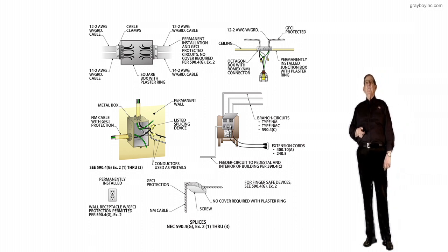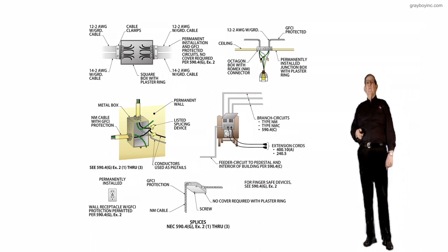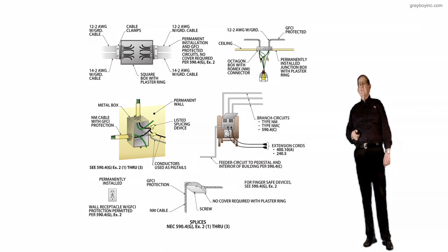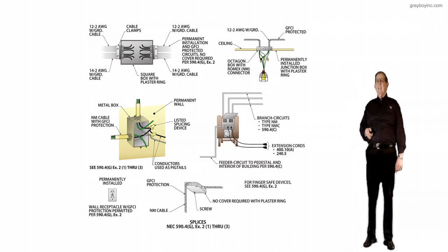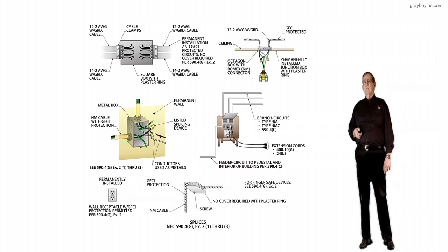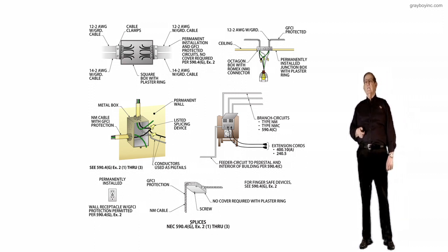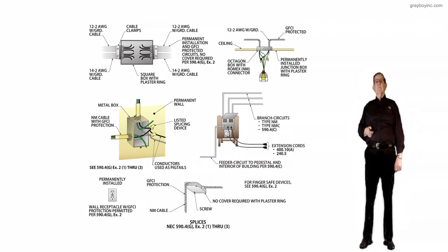But now when it's permanent and we're going to keep it out there as a permanent means, then we need to have the cover on it because OSHA, 70B, 70E, and the NEC, all these standards and codes do not allow exposed terminations, conductors, and splices and things of that nature.